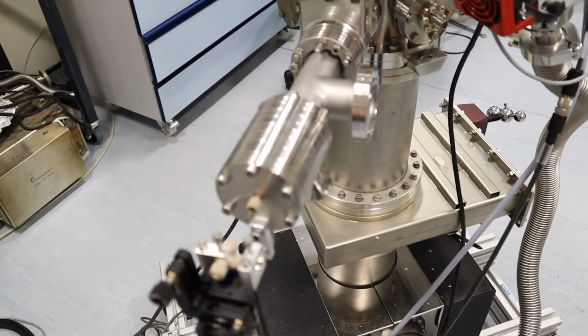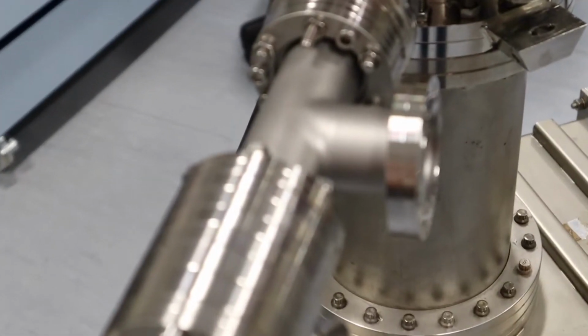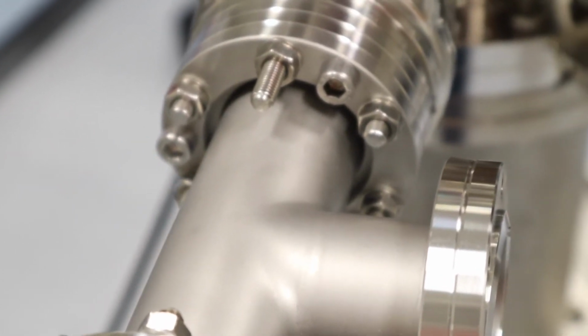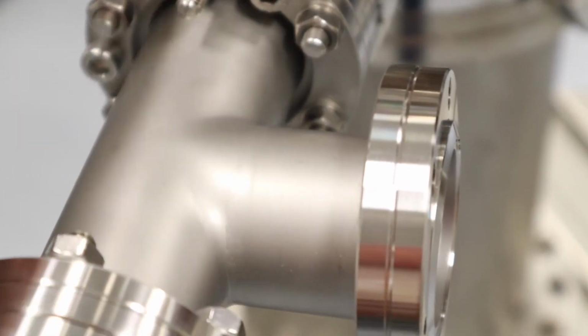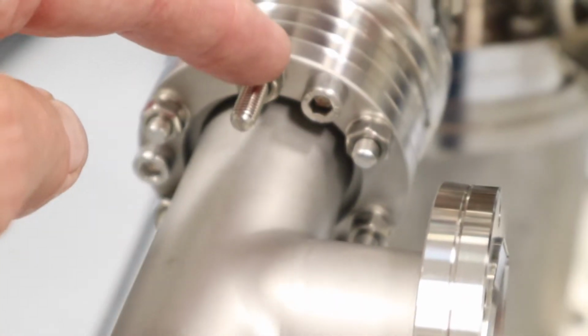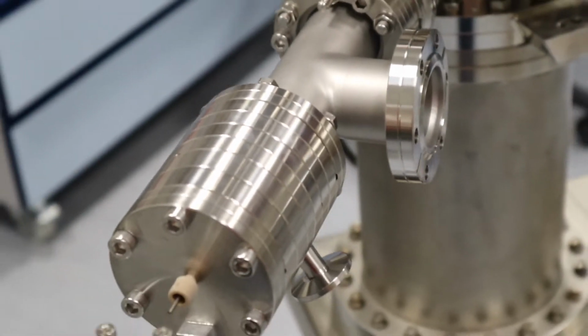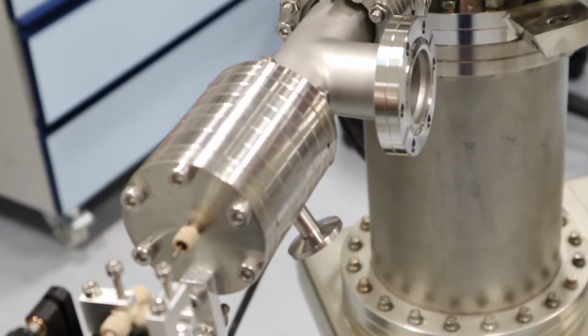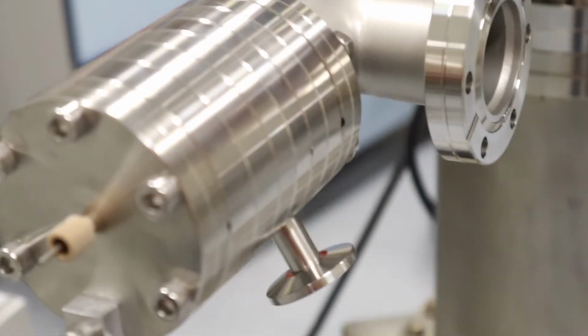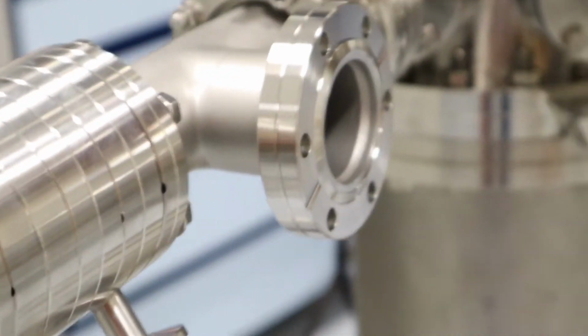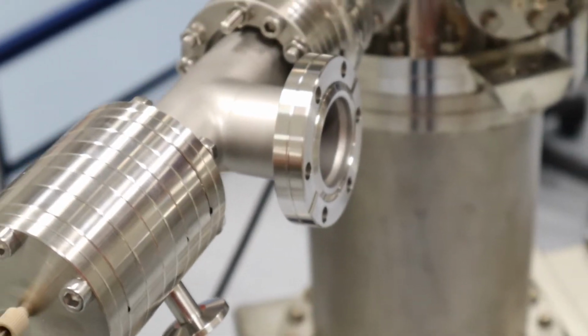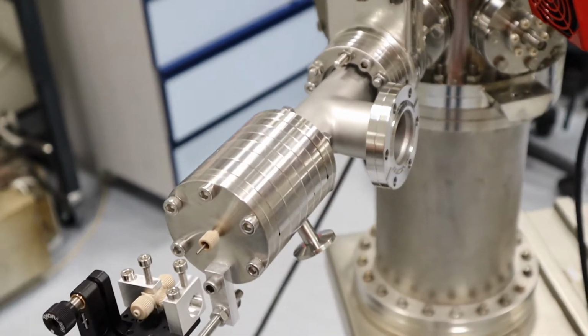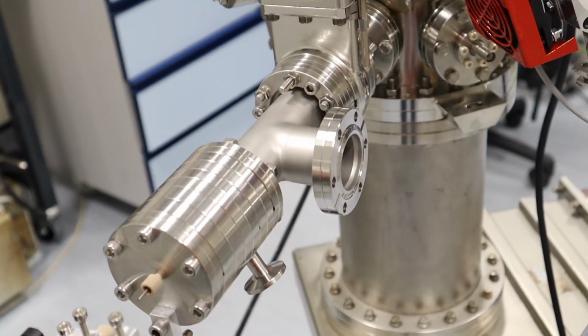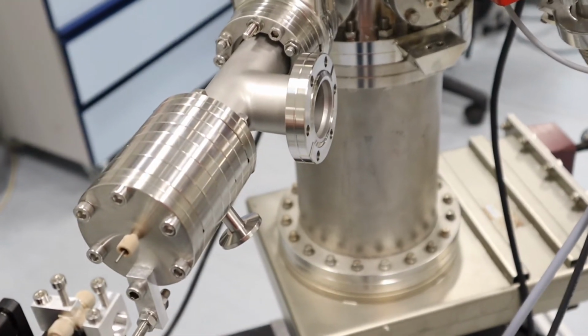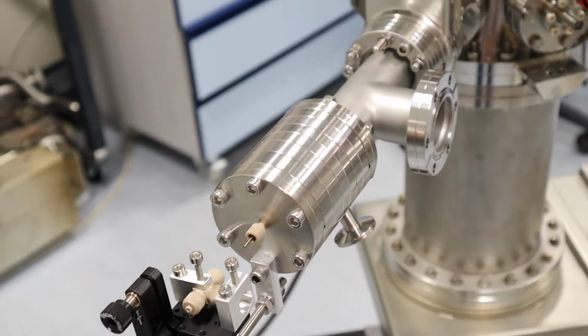Okay, so now I've mounted the electrospray on the valve, and the 6 nuts are tight on the pin bolt, and I did tighten these socket cap screws just a little bit, and you can see I have this in the orientation where the stage 1 and 2 ports are pointing downwards, and the turbo pump port for stage 3 is horizontal. The electrospray itself is now horizontal as well. None of that matters. I could have mounted it in any orientation. This is just convenient for attaching the pumps.